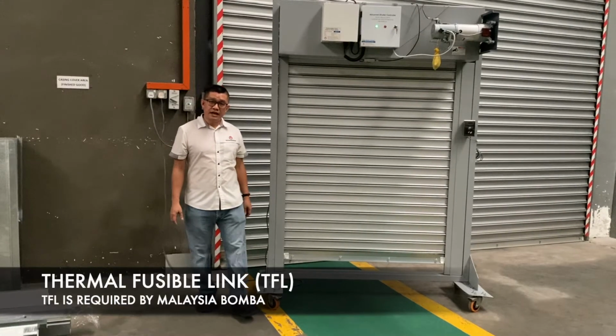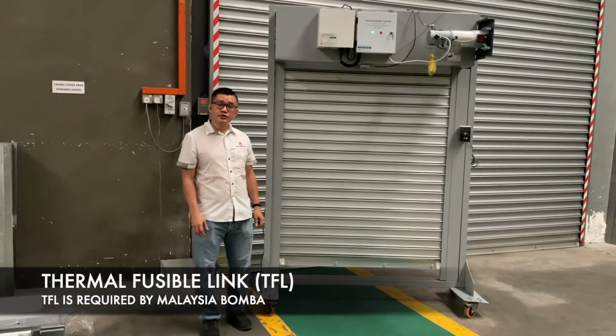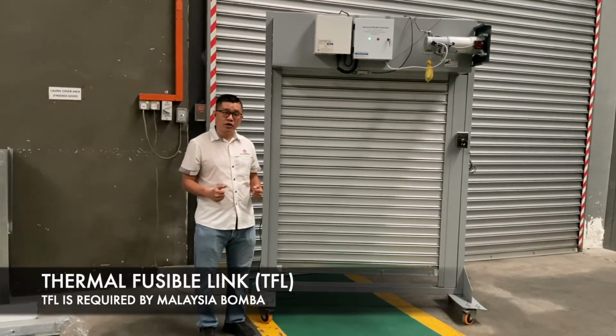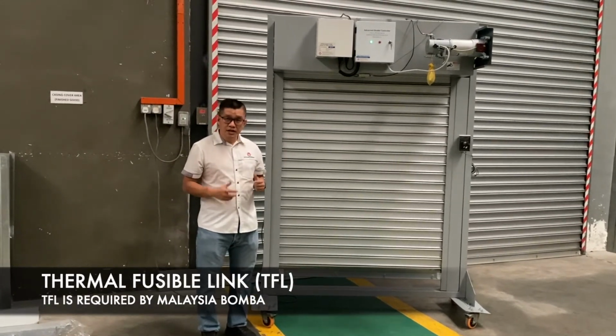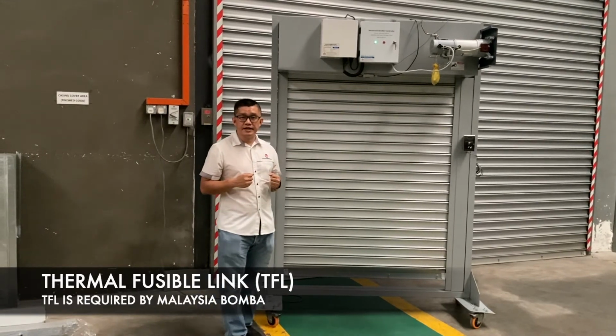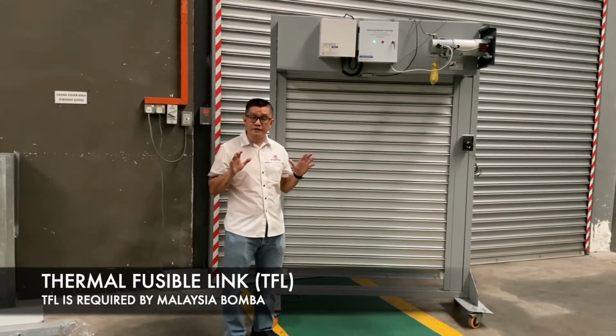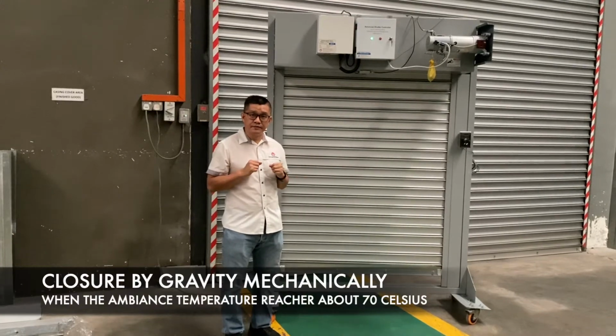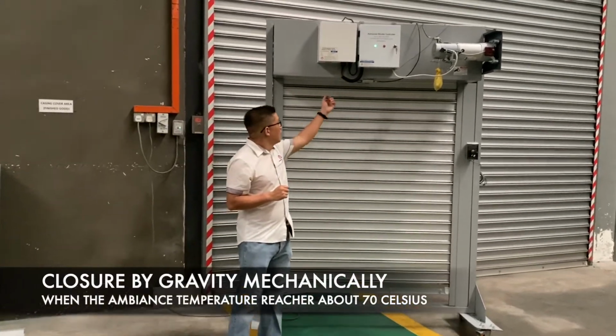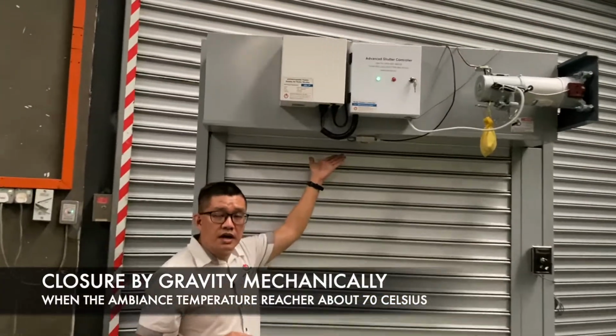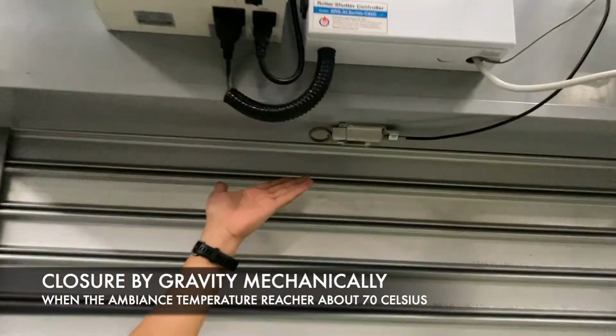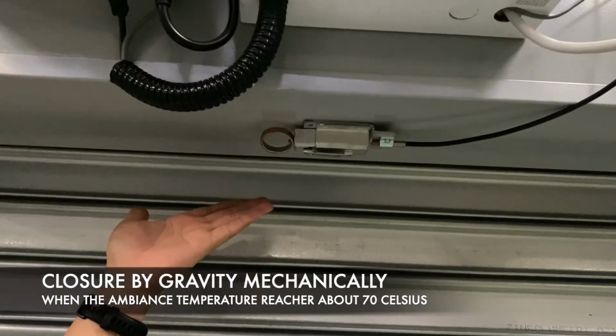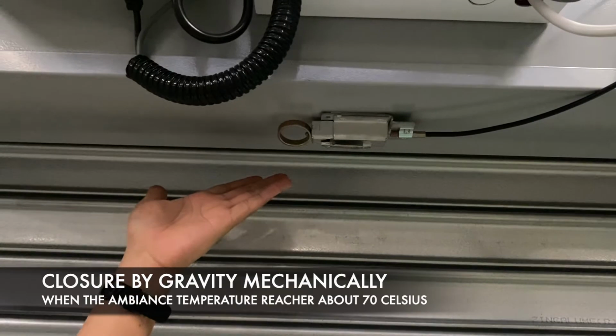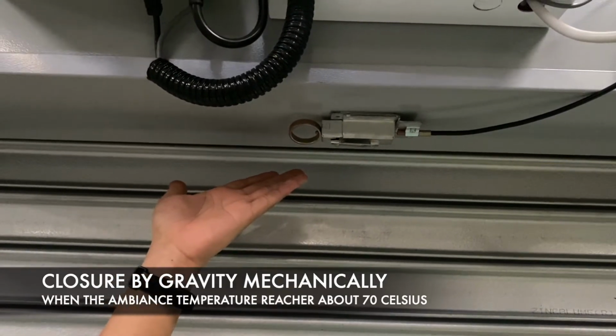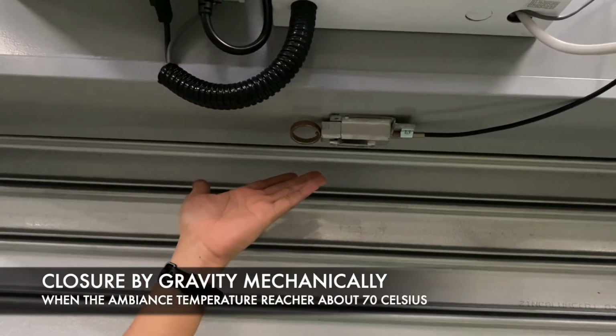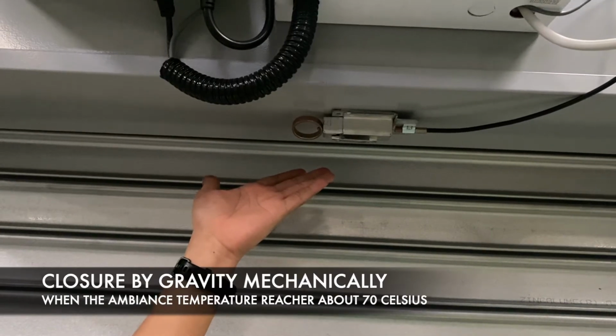In Malaysia and most countries, a thermal fusible link is required by law for fire shutters. The purpose of the thermal fusible link is to ensure the closure of a fire shutter in the event of fire. When the temperature around the thermal fusible link reaches about 70 Celsius, the shutter will close automatically by gravity, even without electrical power.